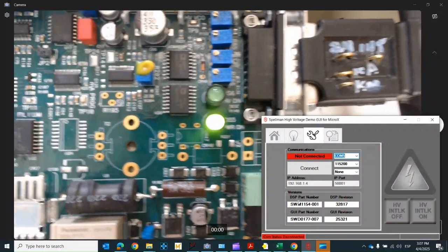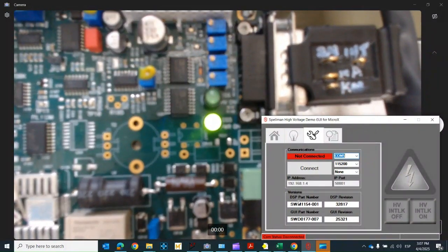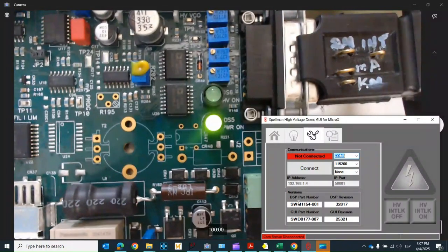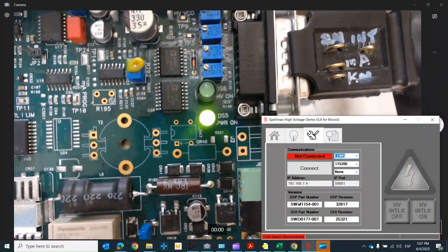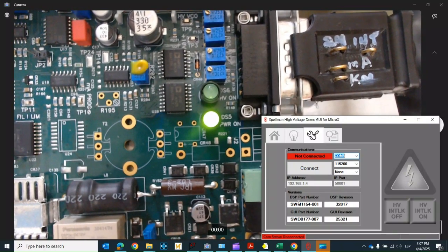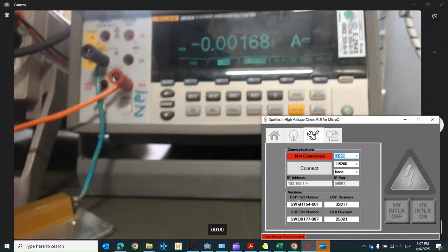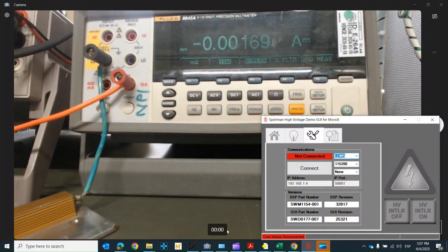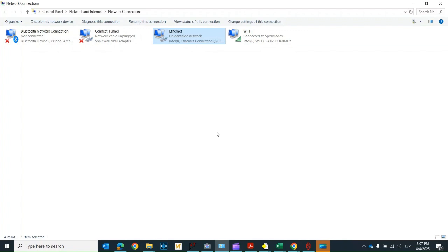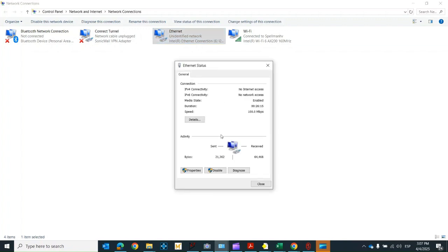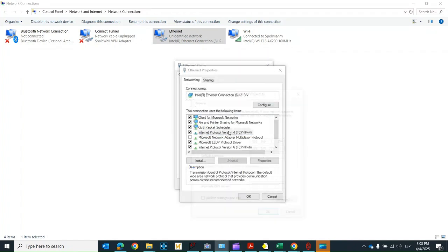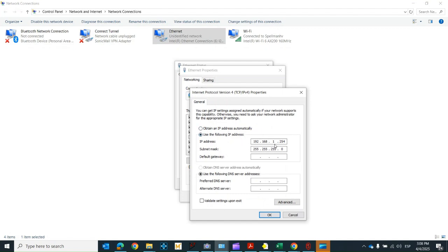as this will tie the analog outputs of the processor being used for the digital communication to the Micro X control signals. It can also be shown that, as mentioned in the previous schematics, a jumper connected to the 15-pin connector that still has the 270 ohm resistor in series with the interlock connection is used. Another thing to remember is that, before connecting through the Ethernet protocol to the X6417, the user must ensure that the computer's IP address is configured to 192.168.1 and other 3 numbers.